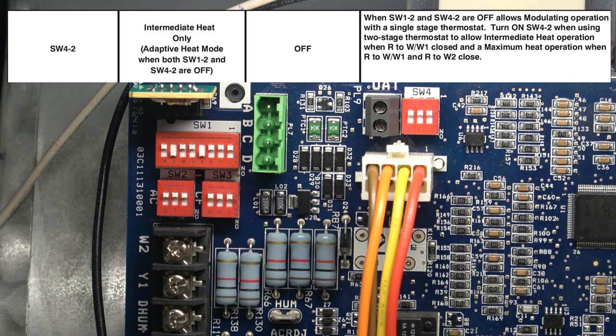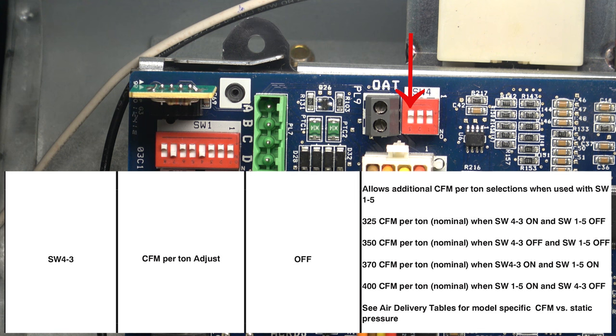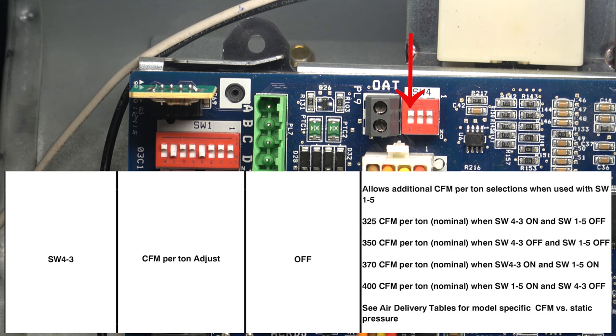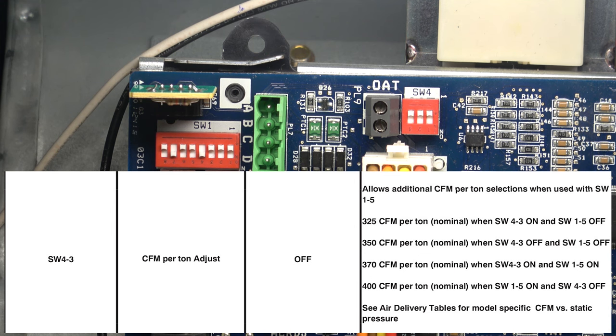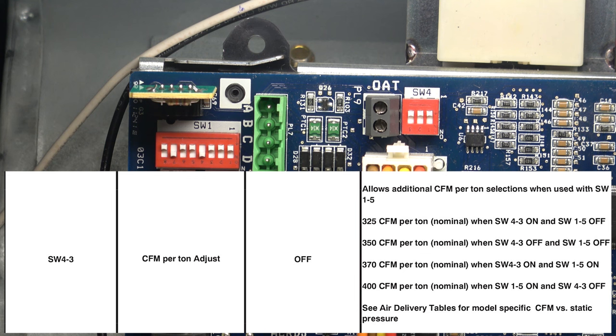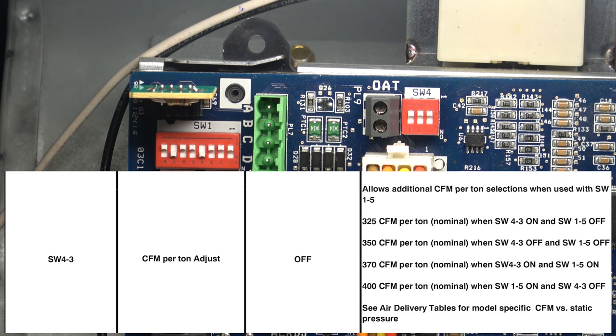Moving on to switch four number three, that is the CFM per ton adjustment switch. This works along with switch one number five. It allows additional CFM per ton adjustment when used with switch one number five. Switch four works together with switch one. The combination of those switches determines the CFM per ton allowed, from 325 CFM per ton to 400 CFM per ton. We are showing the chart for that now.